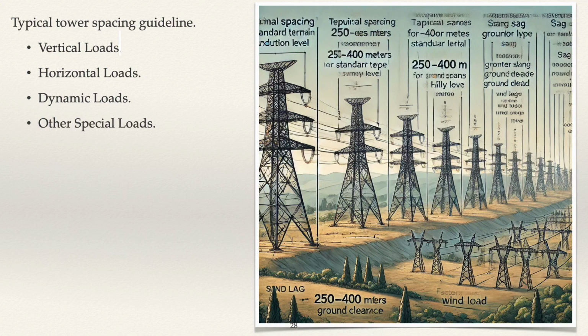2. Horizontal loads, forces that act sideways on the tower, primarily caused by environmental factors. Components of horizontal loads are: A. Wind load, pressure exerted by wind on the tower, conductors, and insulators. This is a significant factor in tower design. B. Conductor tension, horizontal pulling forces due to the tension in conductors and shield wires, especially at angle or tension towers. C. Ice load in cold regions, the weight of ice accumulation on conductors and the tower, which creates both vertical and horizontal loads due to wind acting on the iced surface.